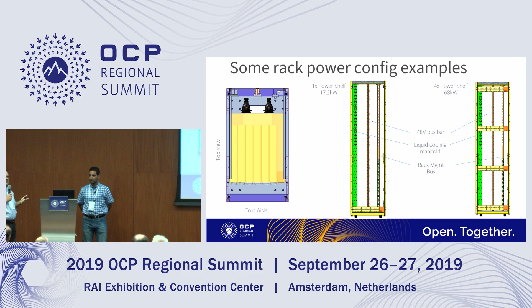Open Rack V2, which I co-authored with other folks a few years ago, got a lot of feedback from the community that this voltage range is too wide, 40 to 60. Designing a rectifier with a nominal of 54 that also works down to 48 volt is difficult. The bus bar has to be designed with a nominal of 54, but it also needs to work with 40 volt, meaning 54 divided by 40 is like 36% more. So the bus bar should be thicker by 36%, and so should the connectors and everything.